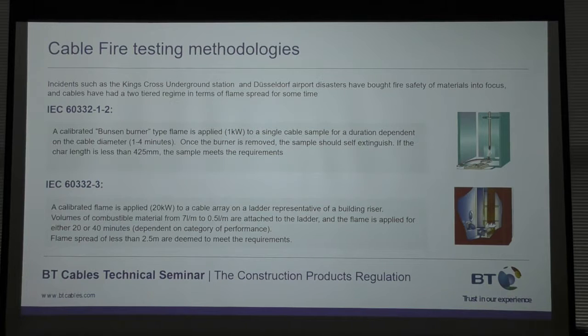So this is just a brief history on the cable fire testing methods and what the CPR is doing differently. The baseline for fire safety is IEC 60332-1-2, which is basically a Bunsen burner flame applied to a single solitary piece of cable, and there is a char limit - the cable must be self-extinguishing. That's the most basic fire safety requirement in cables.